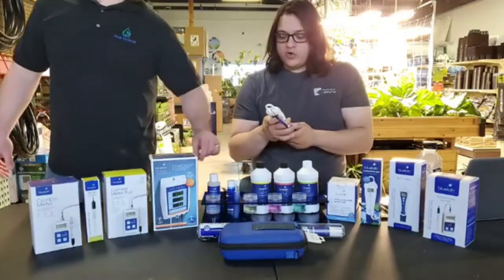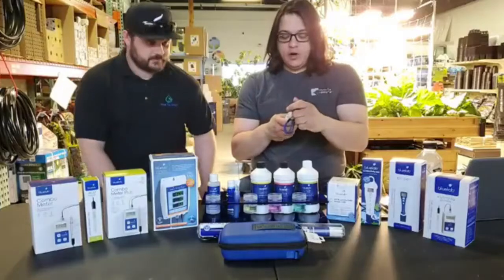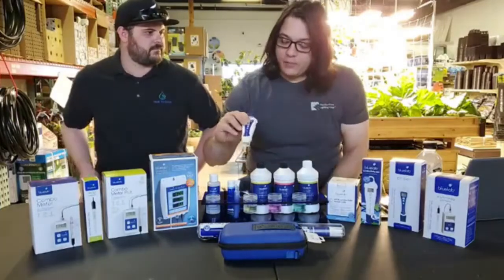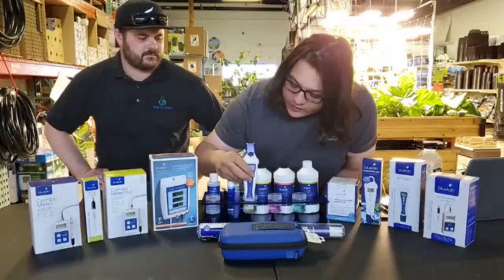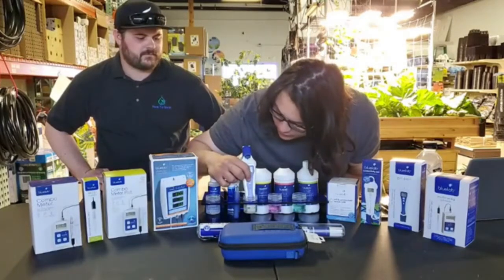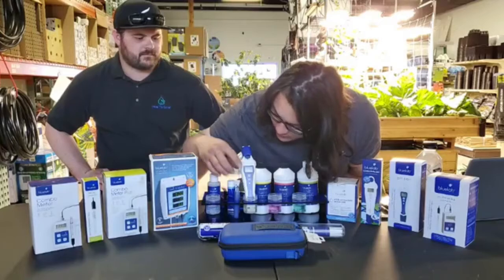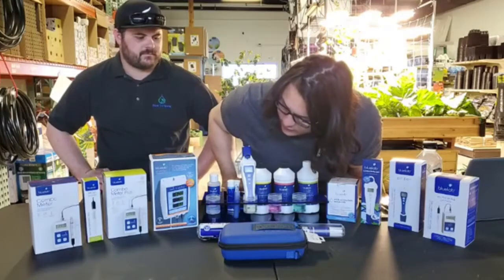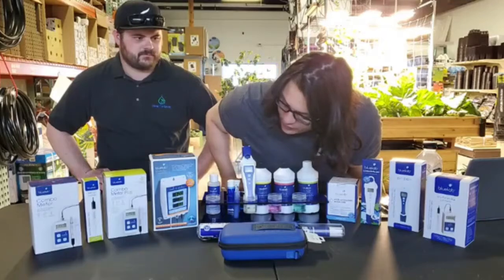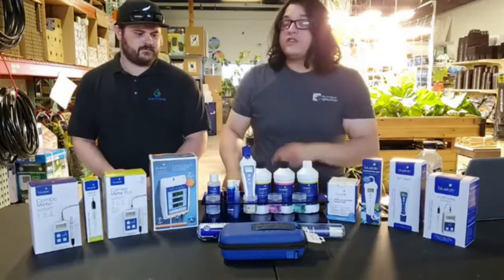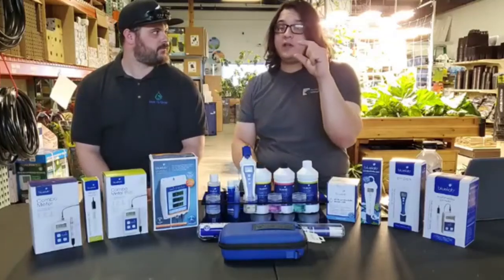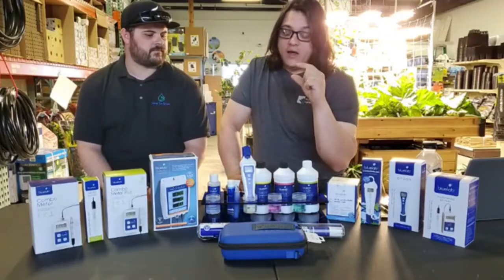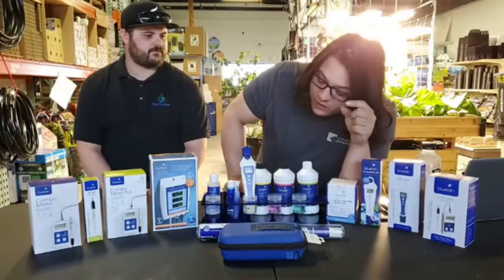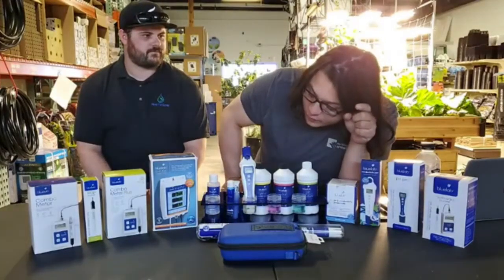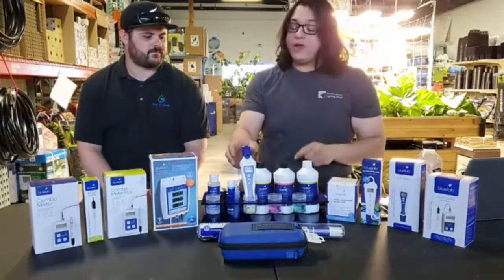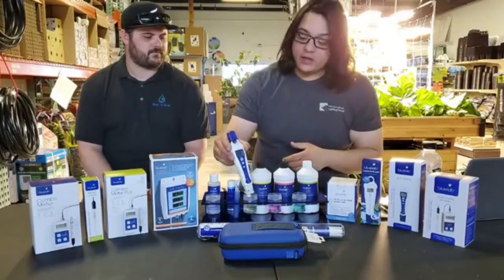Just a little control rinse water. That's just to rinse the probe off in between calibrations. So put the cap on the top, and then we are going to put it in the solution. Hold the calibration button for about 3 seconds. It'll say cal. It's going to think. And then 4 zeros are going to run across the top of the screen, but on the bottom it should be indicating that it's reading 7. And it should automatically do that. So if it says something else, shut it off and restart it, and make sure that it's on the proper one. And if it's not, there might be an issue with your meter. Bring it into us and we'll let you know.